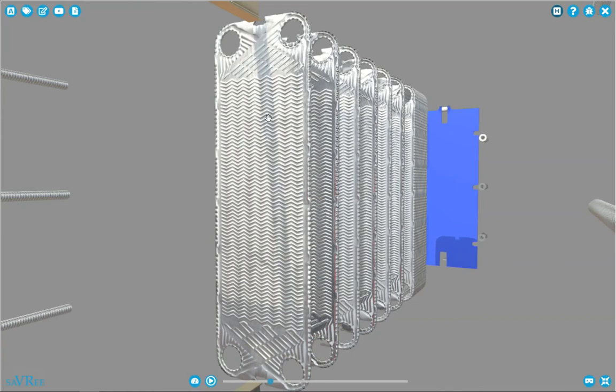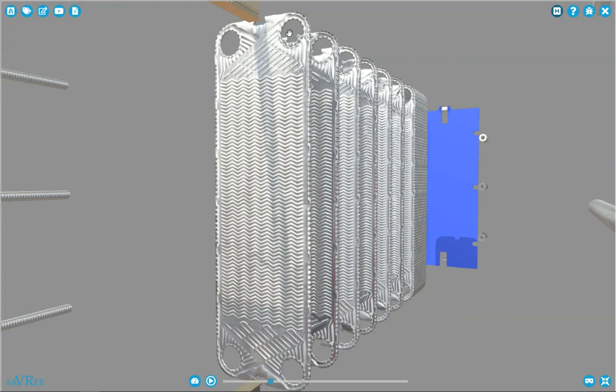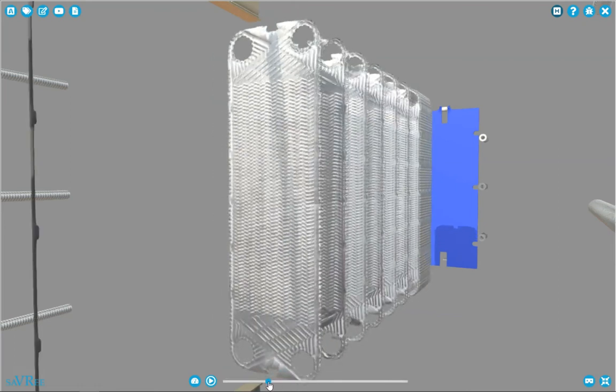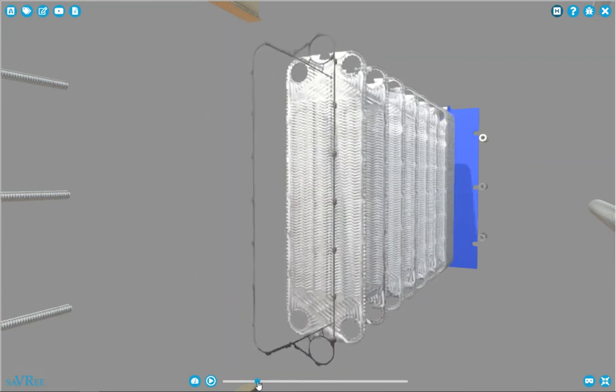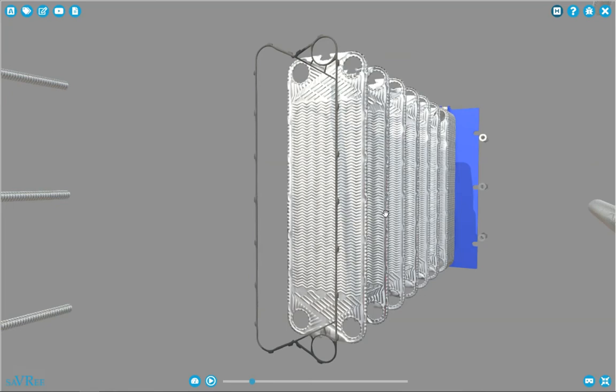So if we looked at how this plate type heat exchanger may work, maybe we had our two fluids that were coming in. So maybe this is fluid A over here and fluid B that's coming in through the frame over here. And then it would be allowed to just mix together and then work their way out. So we don't want those fluids to just mix. So in order to keep them separate, what we have in between each plate is a little rubber gasket. And the gasket material provides separation for each of the flows.